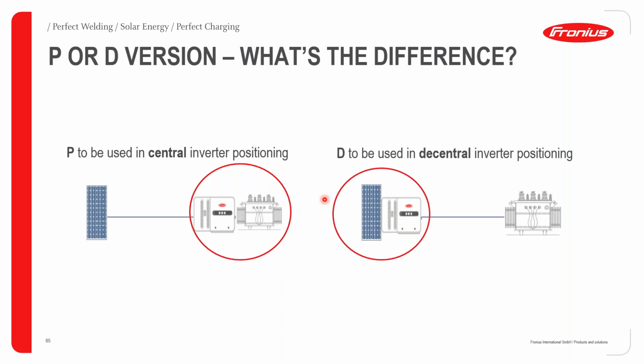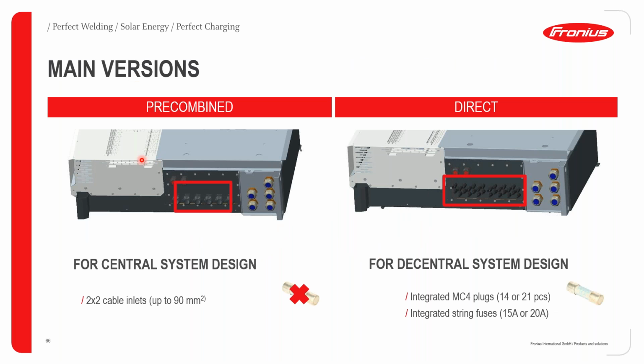In contrast, when you look at the decentral kind of configuration, we're talking about an inverter that has the capability for you to connect all the string connections directly to the inverter. And then from the inverter, we are running a much longer distance of AC cabling. Therefore, for a pre-combined or centralized version, the AC cabling will be much thinner in cross-section than the decentral version, because the decentral version will have a cable running for a much longer distance in the AC connection. And this is the major difference, as you can see in these two visuals here.